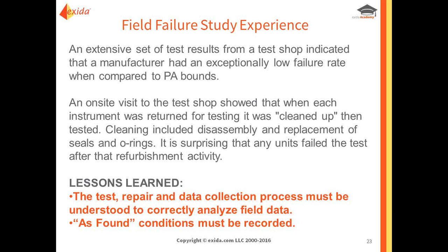Okay, here's what we found. An on-site visit to that test shop showed that when each instrument was returned for testing, it was cleaned up. They didn't think they were doing anything wrong. After they cleaned it up, they then tested it. Cleaning for them included disassembling the product and replacing any seals or O-rings that looked kind of damaged, and then they tested it. We were surprised that they were still seeing failures even after all that work and refurbishment.